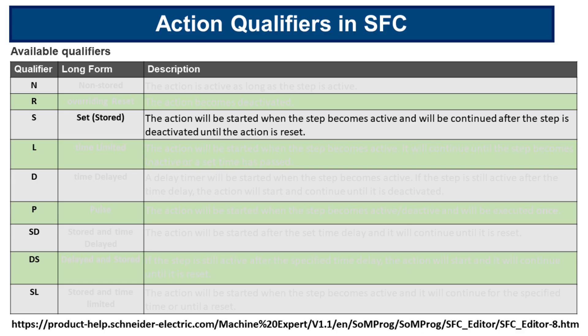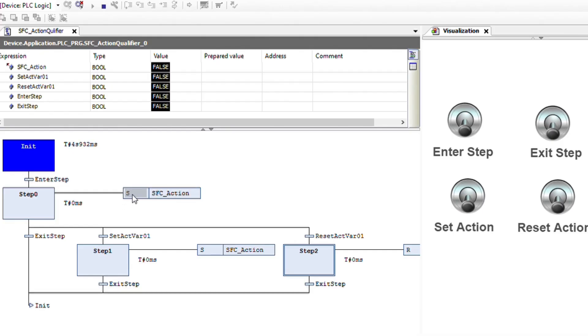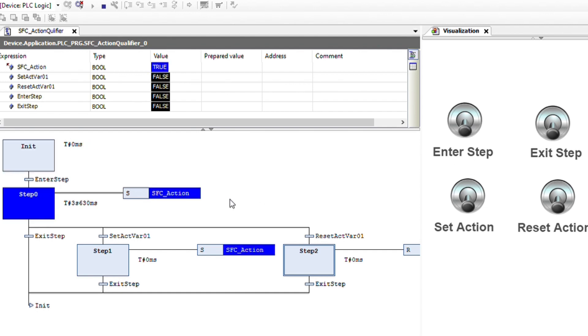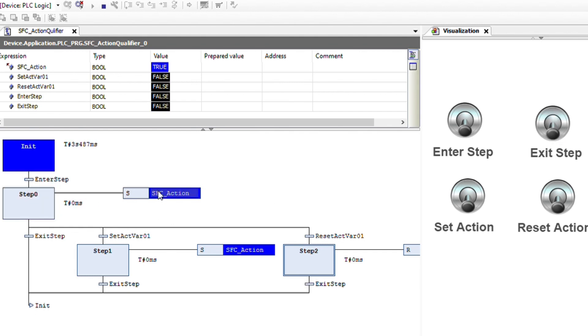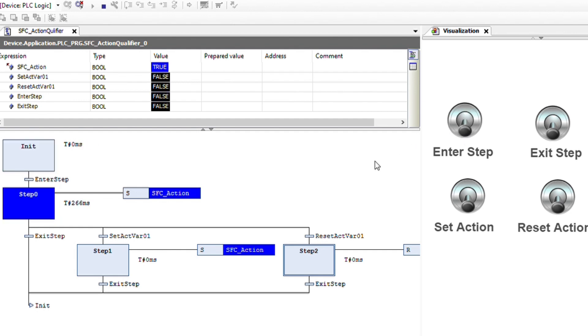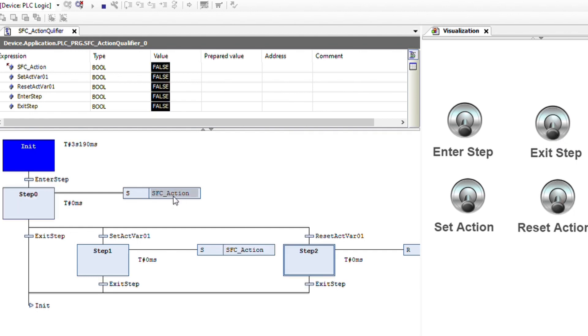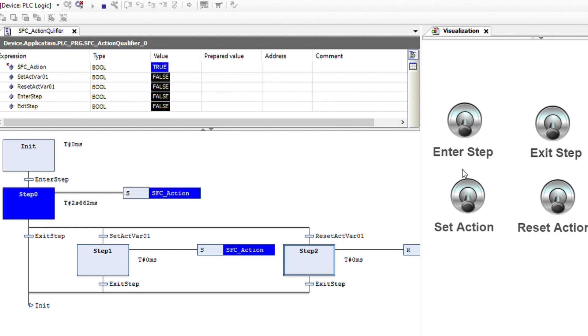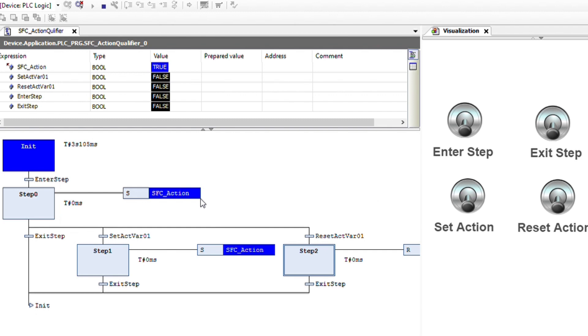Now let's switch to the next one, which is the S qualifier, standing for set or stored. The action will be started when the step becomes active and will continue after the step is deactivated until the action is reset. I have changed the action qualifier to S. SFC action is false. As soon as we enter the step, SFC action will become true. Even if we leave the step and don't reset the action, it will remain true. But if I enter and reset the action and then go back to init, SFC action is false. If we enter into the step it becomes true; if we exit it remains true. That's how the S qualifier works.